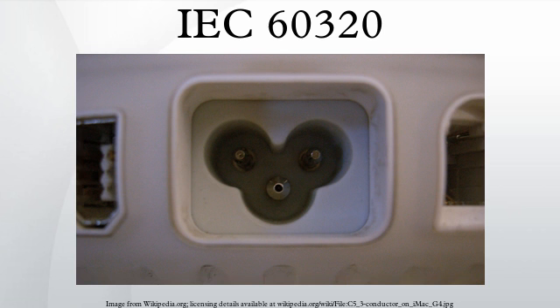Contents of standards: the standards define the mechanical, electrical and thermal requirements and safety goals of power couplers. The standard scope is limited to appliance couplers with a rated voltage not exceeding 250 VAC at 50 Hz or 60 Hz, and a rated current not exceeding 16 A. Further subparts of IEC 60320 focus on special topics such as protection ratings and appliance-specific requirements.